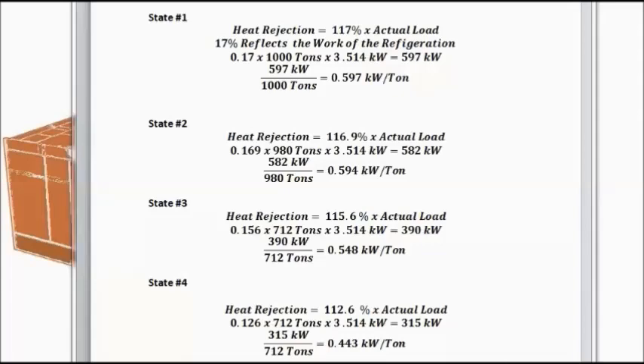So, finally, I think I just want to make a couple of points here. I showed you how variable condenser water flow is controlled by maintaining the temperature difference across the chiller condenser barrel to a constant 10 degrees. The second point was to show, in a different way, the efficiency improvement using condenser water reset. And one more, perhaps peripheral point is to show off the sophistication of the simulator that is used here and that is used to customize the operation of the chiller plant optimizer for different plant configurations.